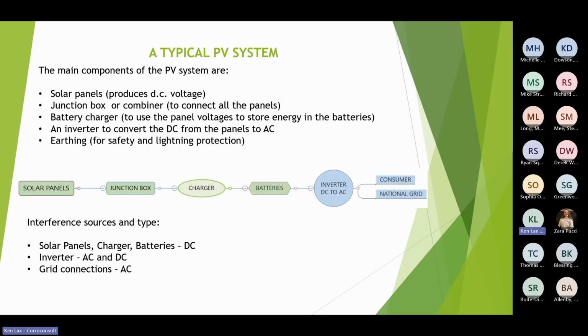Now, I'm going to run through a PV system because it's got a little bit of everything. Basically, you start off with a solar panel that collects the DC. And you think to yourself, well, what is a solar panel? And you think, well, it's just some stuff that sits on a frame that collects juice, and it feeds that juice into a junction box. Well, the first point we have to worry about is the insulation between the solar panel and the frame it's sitting in, because we know from Ohm's law that if there's a low resistance between the solar panel and the frame, and the frame is connected to the piling, and the piling is connected to the earth, there's a low resistance path there for the current to go.